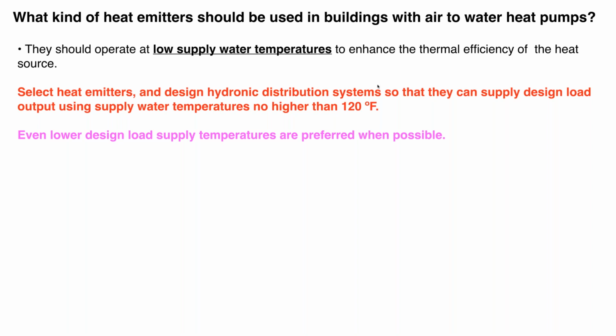The reason for this is, certainly with a heat pump, we want good COPs, but think about future-proofing your system. Today, I can legally design a hydronic system for 180, even 200 degree Fahrenheit water temperature. But going forward, 5 years from now, 10 years from now, if somebody wants to take that boiler that's producing that 180 degree water, take it out and put a heat pump in, they're going to have to do an extensive rework on that distribution system. And we're going to talk about some of those things next week. How can you modify an existing system to bring the water temperature down?